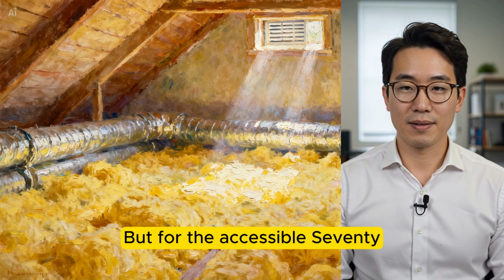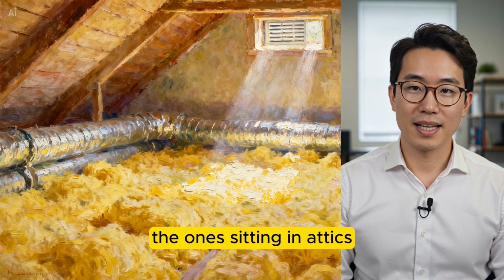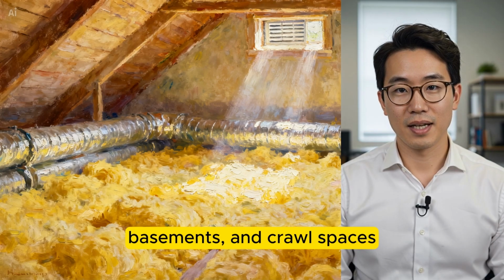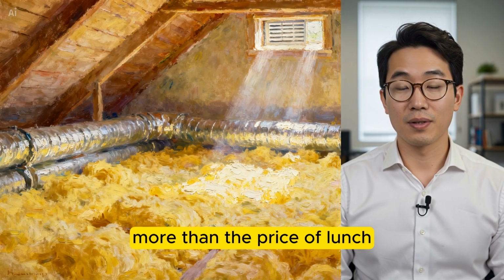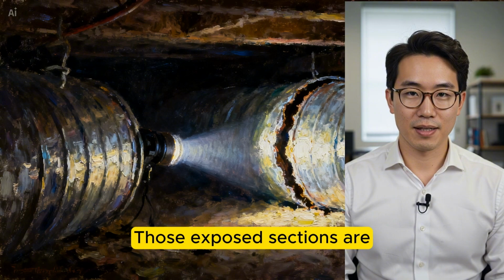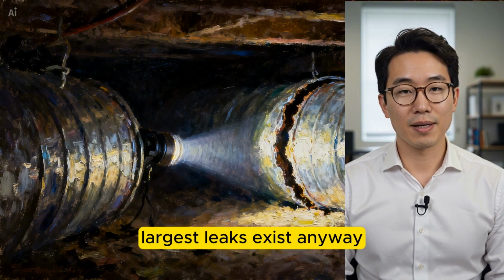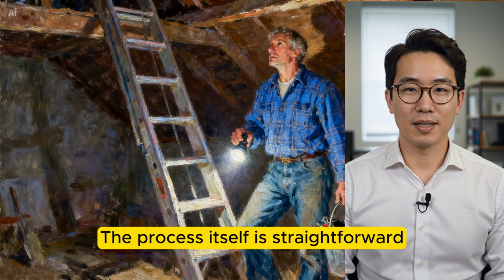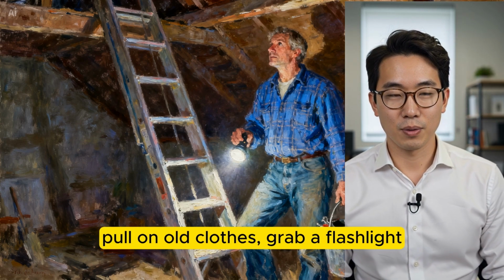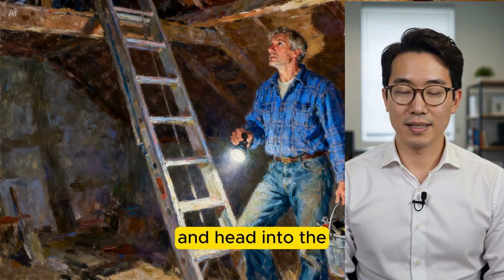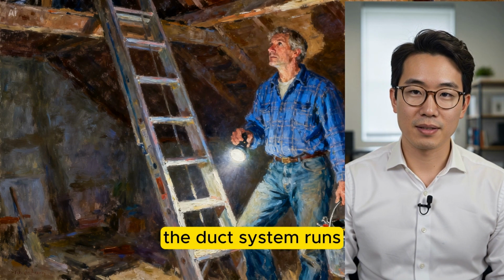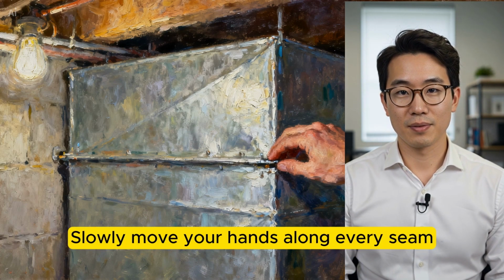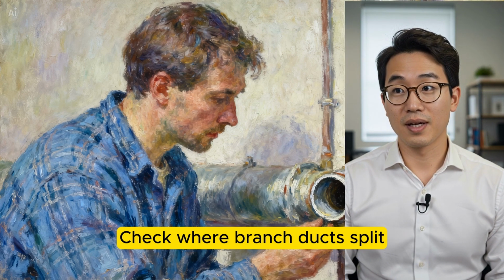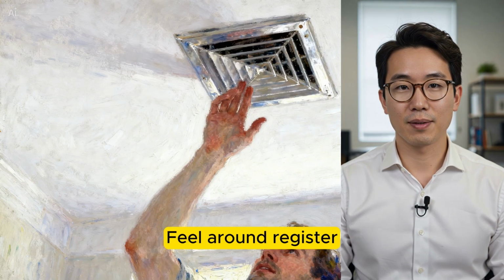But for the accessible 70% of duct joints, the ones sitting in attics, basements, and crawl spaces, the work can often be done personally for little more than the price of lunch. Those exposed sections are usually where the largest leaks exist anyway. The process itself is straightforward. On a Saturday morning, pull on old clothes, grab a flashlight, and head into the attic or basement where the duct system runs. Turn the furnace on. Slowly move your hands along every seam. Check where branch ducts split from the main trunk. Feel around register boots where they meet the ceiling drywall.